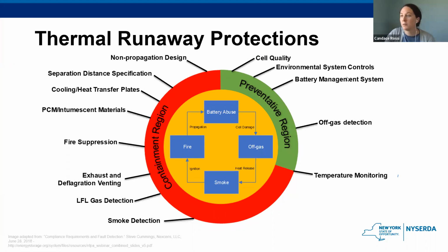So here is the thermal runaway protection. This slide shows that same image, but now with the different protections that are embedded into these projects and are required by standards and codes. In the preventative region, this is where the quality of the cell or the environmental system controls may be able to prevent a thermal runaway event. As we spoke about earlier, the battery management system will be able to detect that the system is not operating correctly and may be able to isolate the issue prior to propagating to the next cell. If there is off-gassing, the off-gas detection system and temperature monitoring should be able to give a warning, and you can prevent the system from continuing into the thermal runaway event.